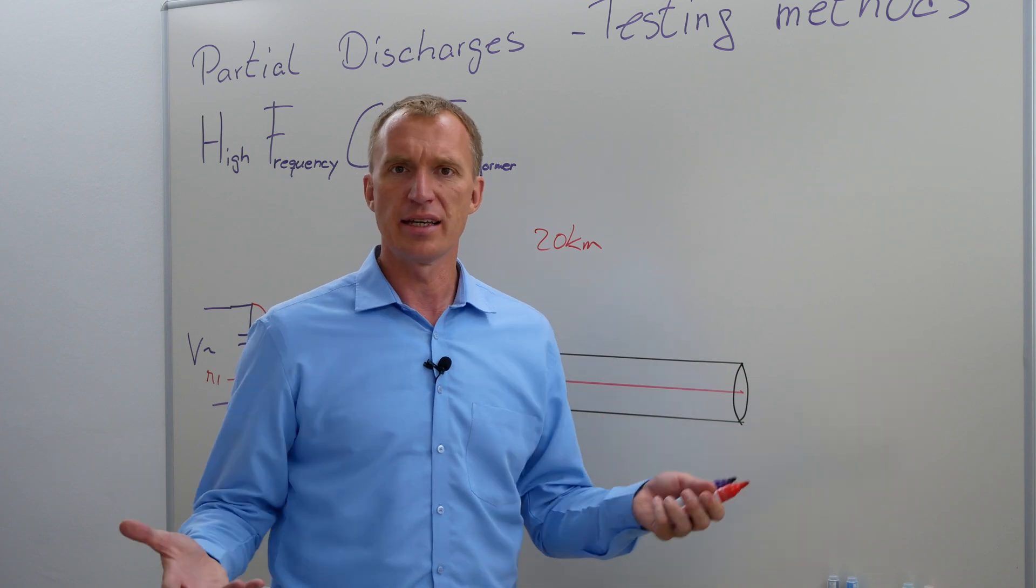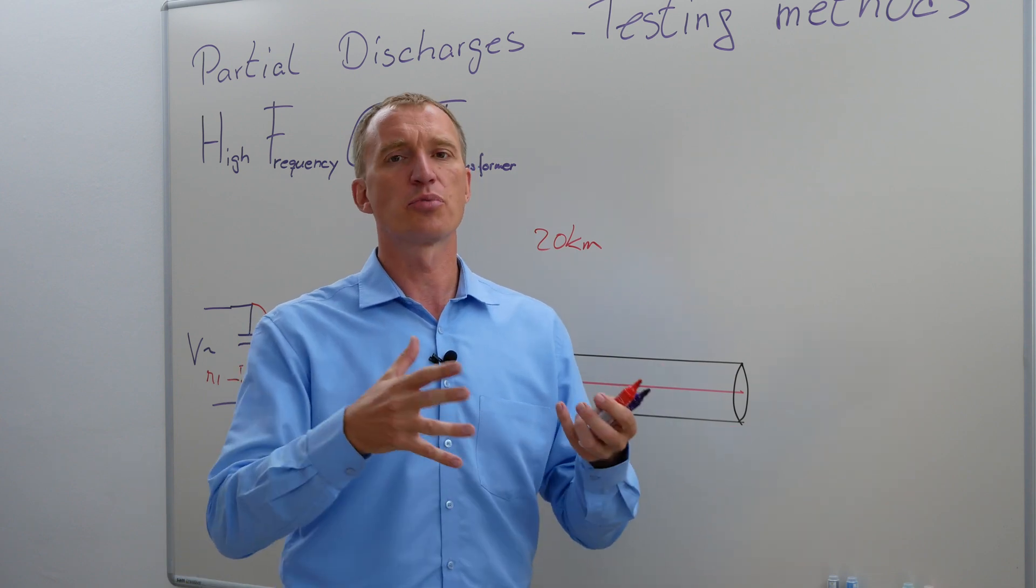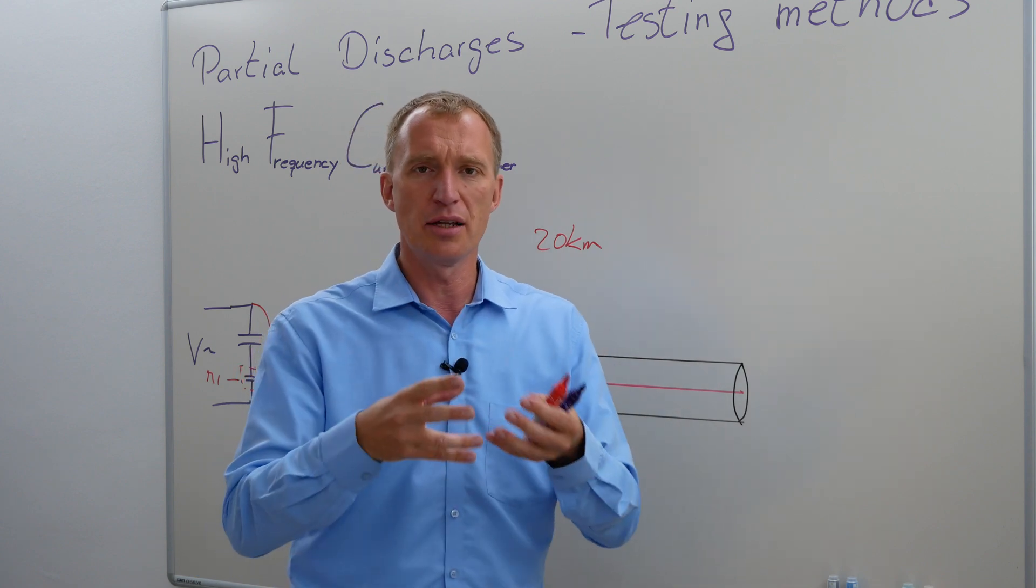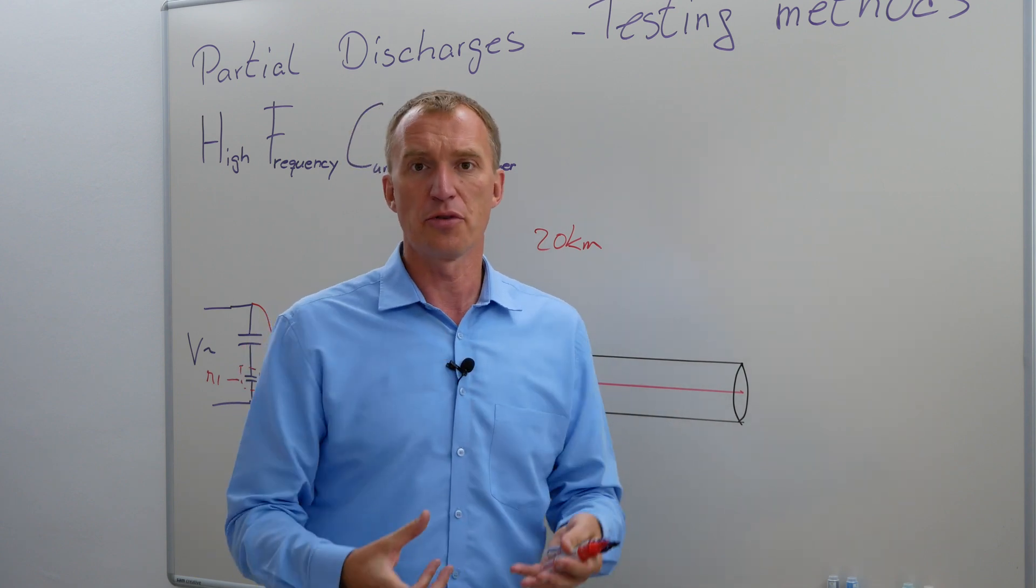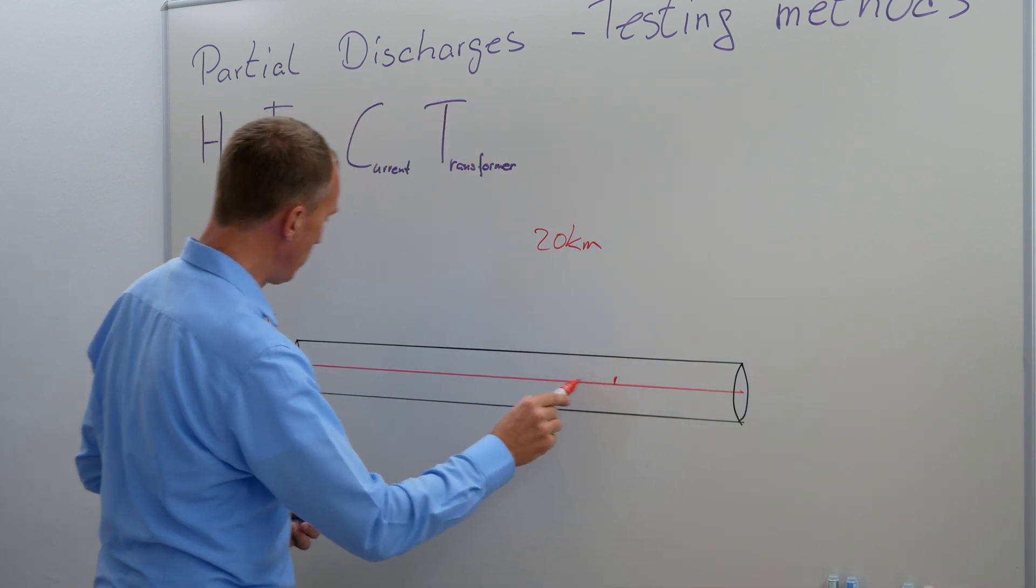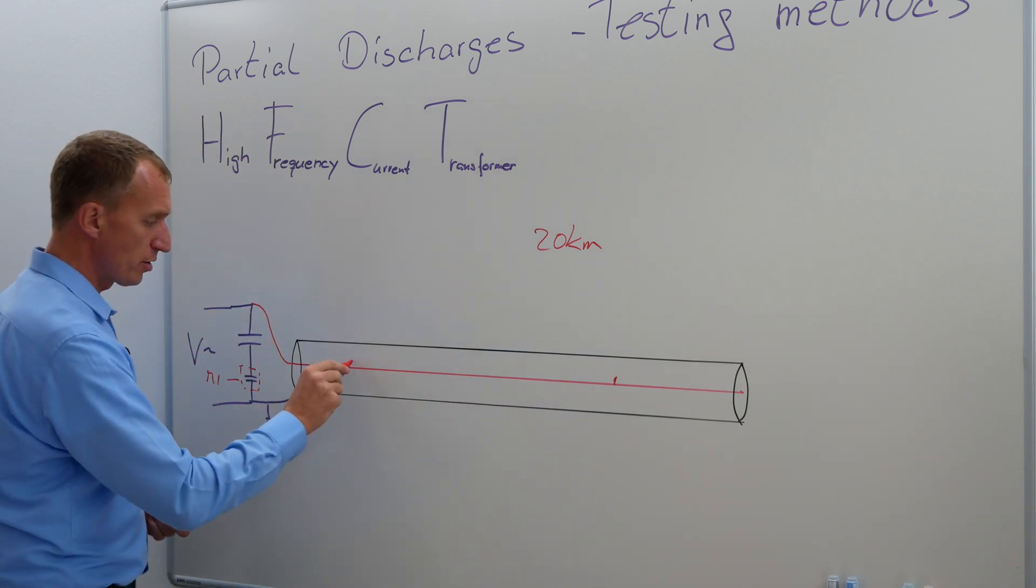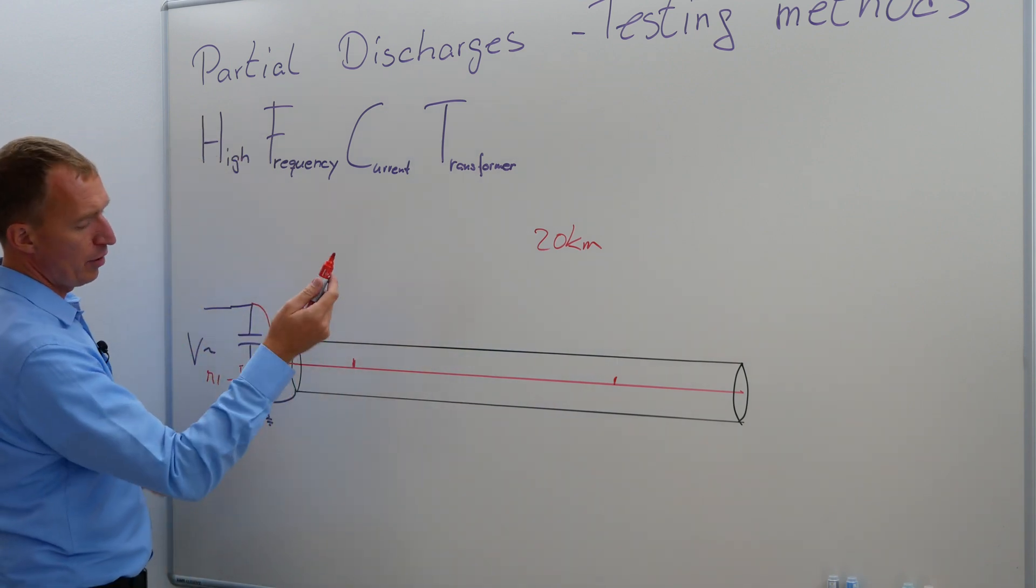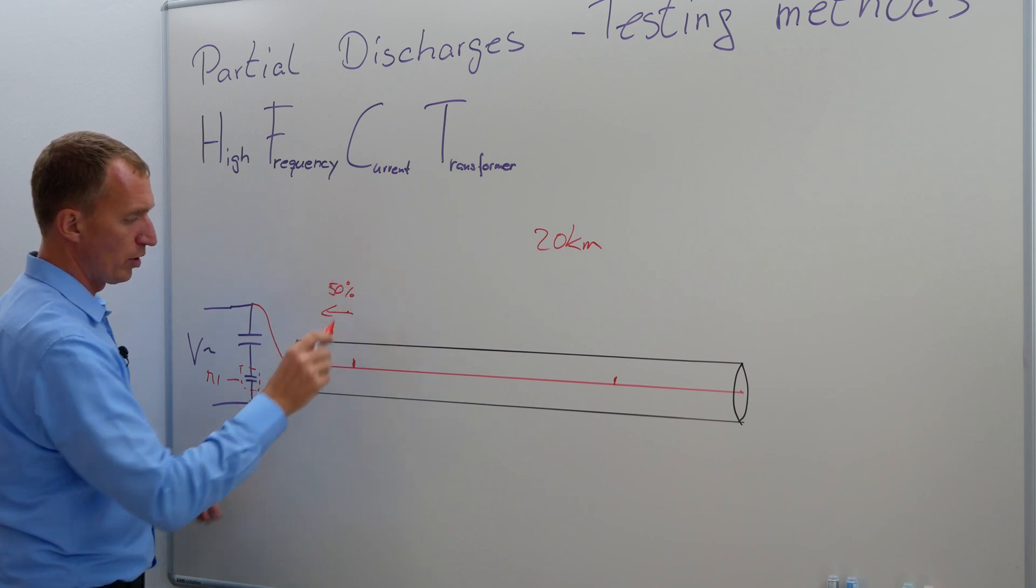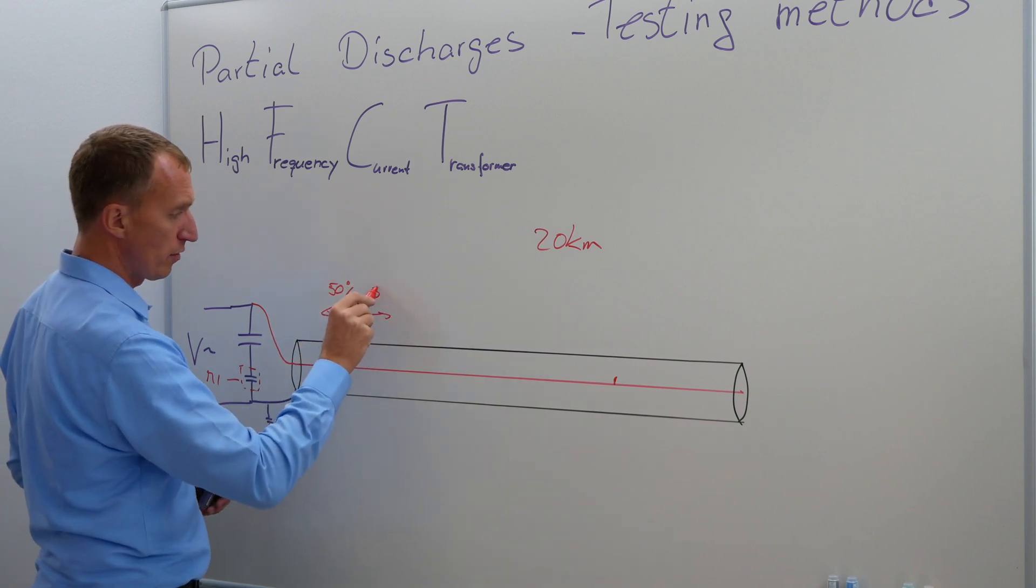However, your background noise is kind of high. And now you have a problem to figure out partial discharge or not. And very often you cannot rely on the fact and or be sure that if a partial discharge happens here, that you really are able to see it. Or even if a partial discharge happens here, about 50% of the charge will travel in this direction, and about 50% of the charge will travel in this direction.